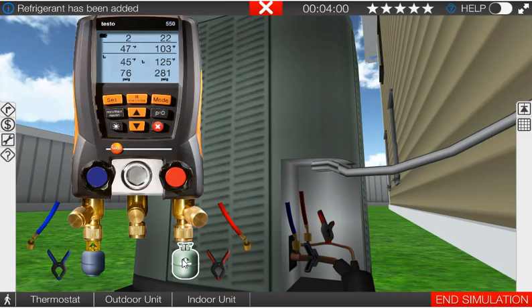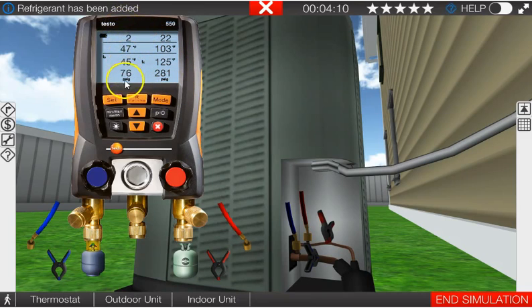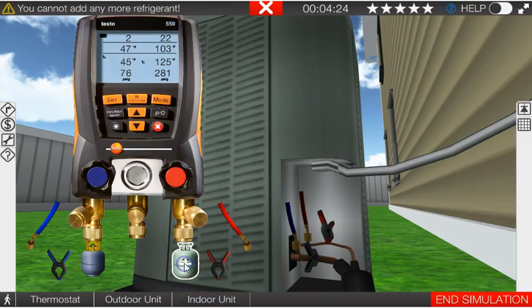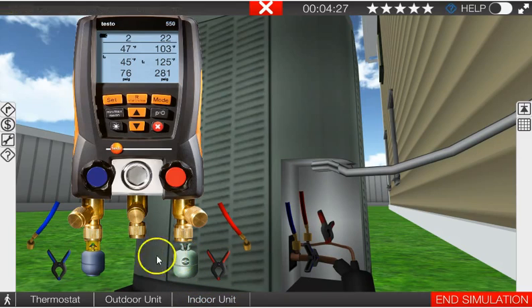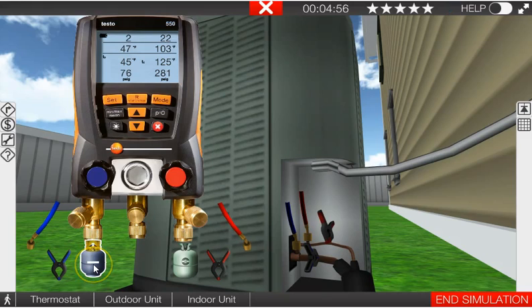So as you add refrigerant and you overcharge a system, subcooling increases, high side pressure increases, superheat decreases, and the low side pressure increases. So you know, if you're new to HVAC and you think that adding refrigerant makes things run better and run colder, that is not the fact. You can see what happens when we overcharge a properly operating system.